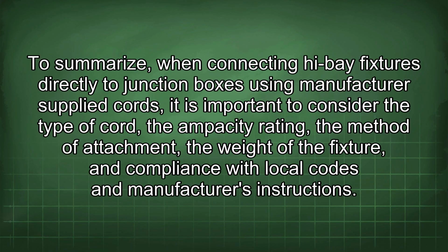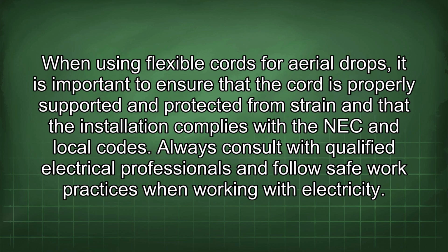To summarize, when connecting high bay fixtures directly to junction boxes using manufacturer-supplied cords, it is important to consider the type of cord, the ampacity rating, the method of attachment, the weight of the fixture, and compliance with local codes and manufacturer's instructions. When using flexible cords for aerial drops, it is important to ensure that the cord is properly supported and protected from strain and that the installation complies with the NEC and local codes.